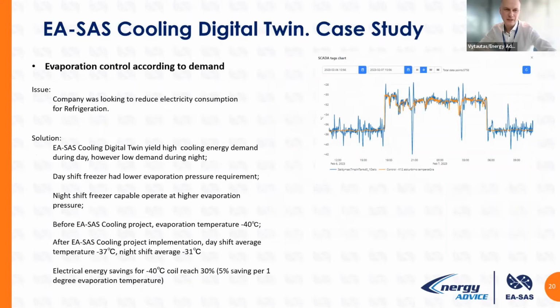In another case, the company was also looking to reduce electricity consumption, and we found that the evaporator was working at -40 degrees. But because we calculate the energy demand, what the cooling energy demand is, what the consumption is, we found that during the night shift it drastically reduces, and we absolutely don't need such -40 temperatures. So yellow is the control set points. You can see it also varies slightly during the night according to need, but the variation is lower, and during the day we work at quite a fixed level.